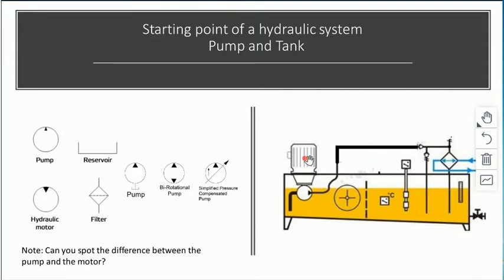It's a bit like your voltage. When you've got a car battery and you turn on your headlamps without the alternator going, the voltage is going to drop a little bit, because the battery can't supply it, or there's some sort of internal resistance and it loses a bit of voltage. Then when you turn on your engine and the alternator is going, it has a regulator, which is a bit like this pressure compensation, an equivalent. The regulator will try to keep the voltage at 13.8 volts at all times, regardless of what you're running. It's a similar thing, so it tries to maintain the pressure. Most industrial systems will use pressure compensated pumps. Okay.